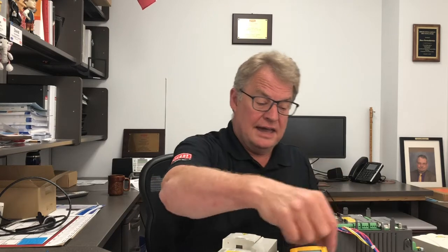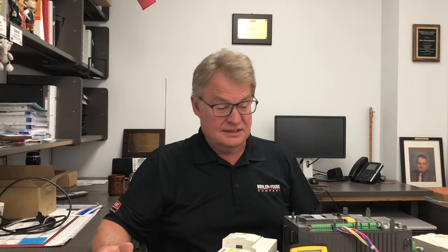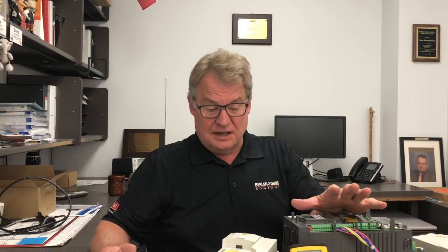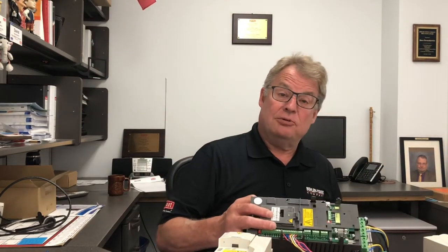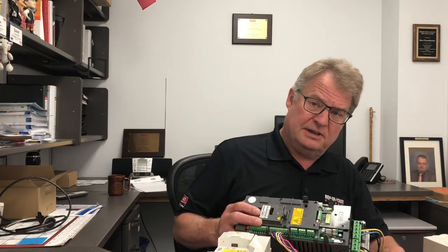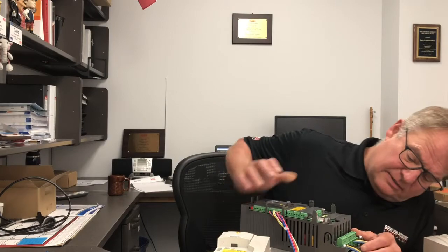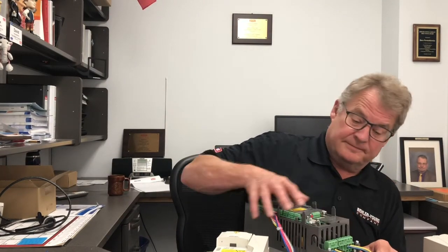All right, so I just checked here. And let's say between pink and white, I have no voltage. So from ground to white, I have 24 volt DC. So that means I should be running my high-speed blower. Okay, so next, we're going to look at the outputs right here. So here's first my AC coming in, and you can see it's plainly marked main, AC coming out, and it says motor.